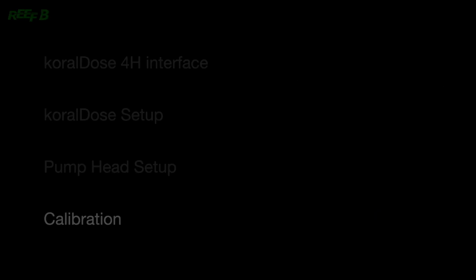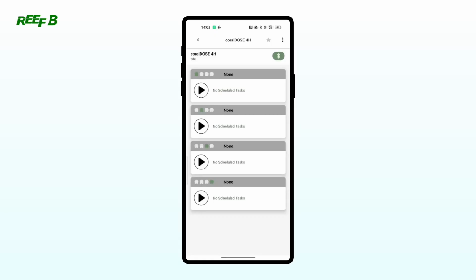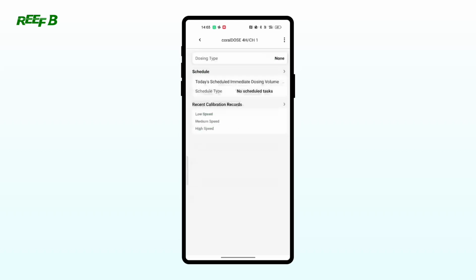Calibration. Pump heads should be recalibrated after a period of use. Frequent calibration helps improve the accuracy of the dosing pump, and it is recommended to recalibrate at least once every month, 30 days. On the koralDose main page, tap the blank area to the right of the pump head to access the pump head settings. Press the next icon next to Recent Calibration Records to begin calibration. Then, tap Calibration in the top right corner to proceed.